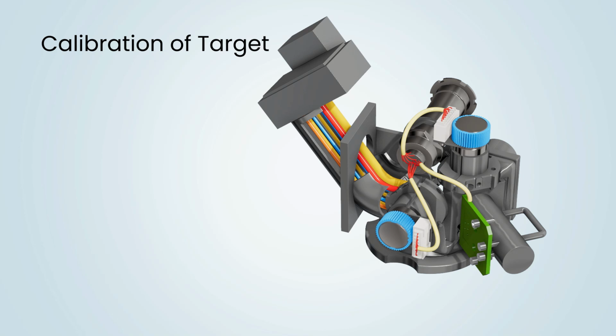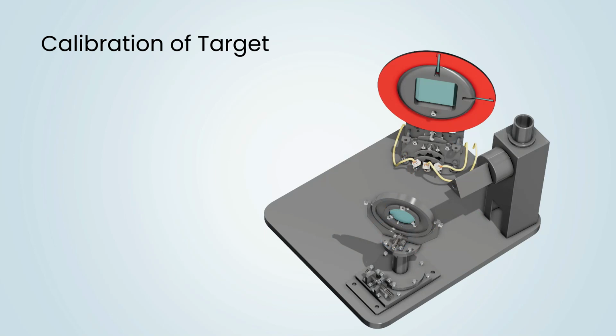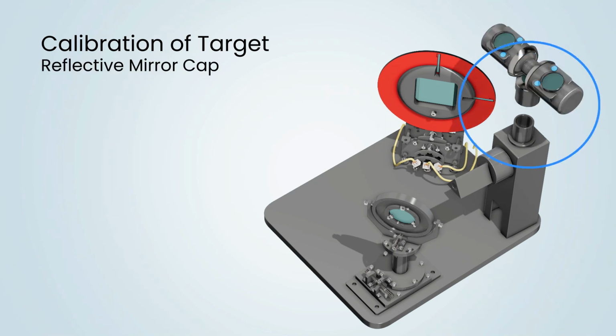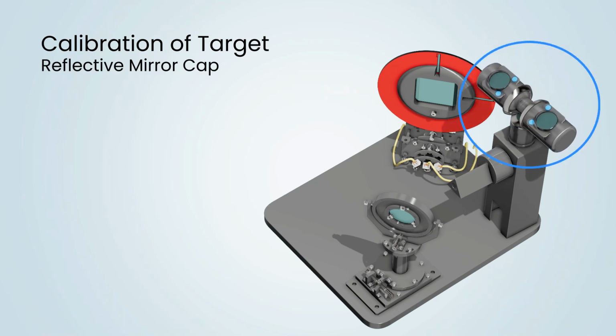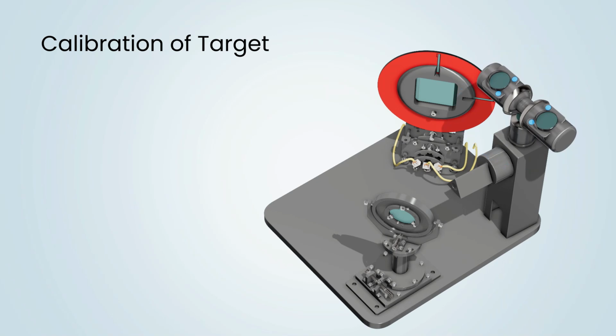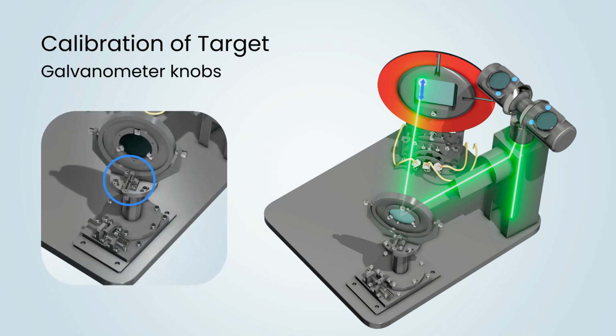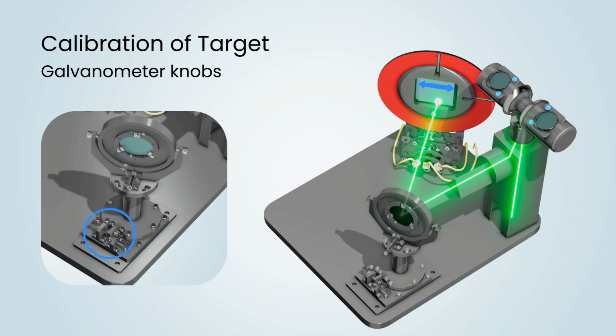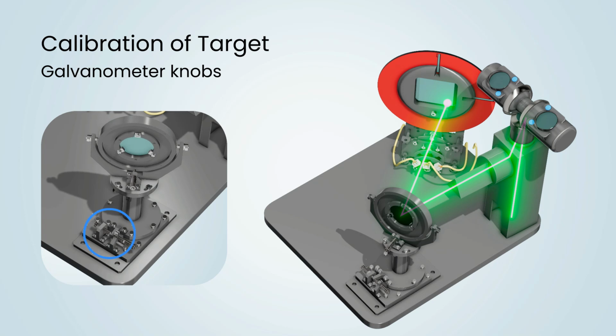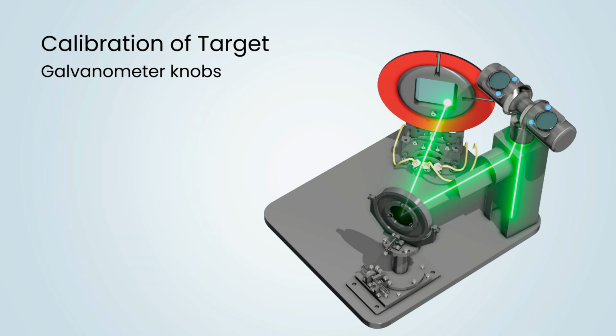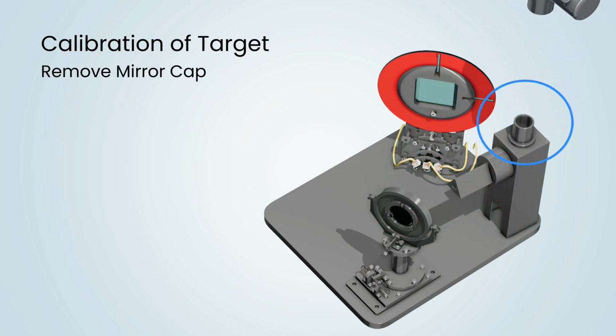Now, for the next part of this process, we will turn our attention to the calibration target. To begin calibrating the target, place the reflective mirror cap over the target and securely fasten it by tightening the screws. The laser point will appear on the target. Move the point by mechanically adjusting the galvanometer knobs. Vertical adjustment is done with the upper galvanometer. Horizontal adjustment is done with the lower galvanometer. Adjust the laser so it hits the target area precisely in the center. Once centered, remove the reflective mirror cap.